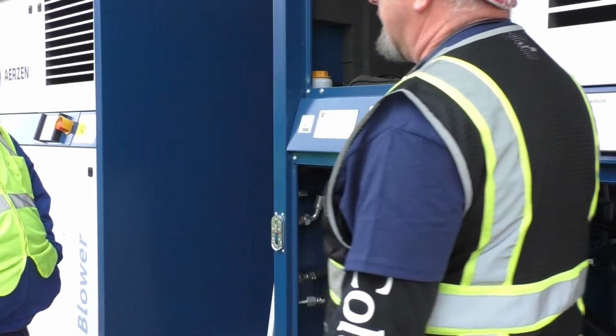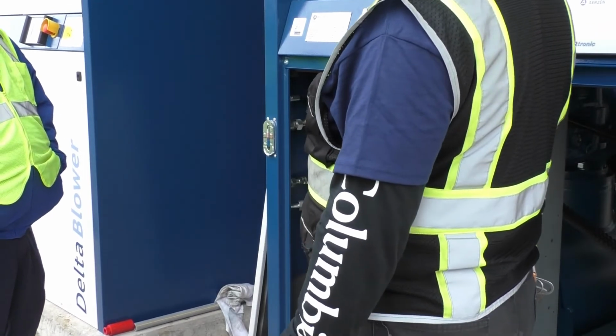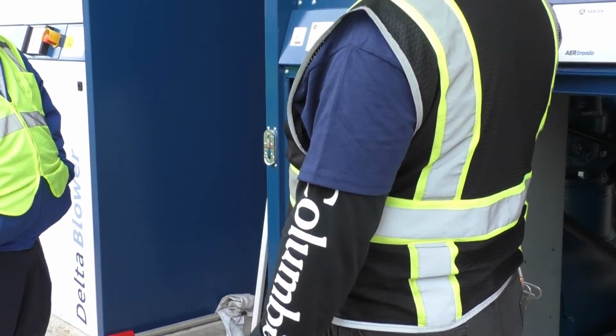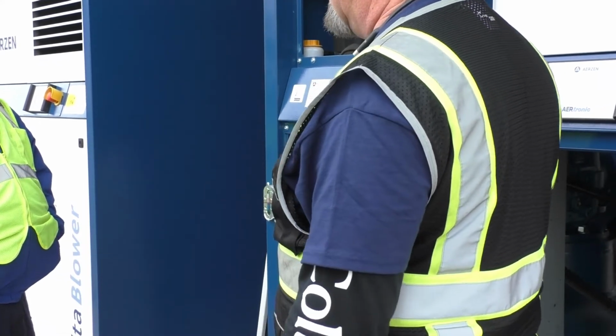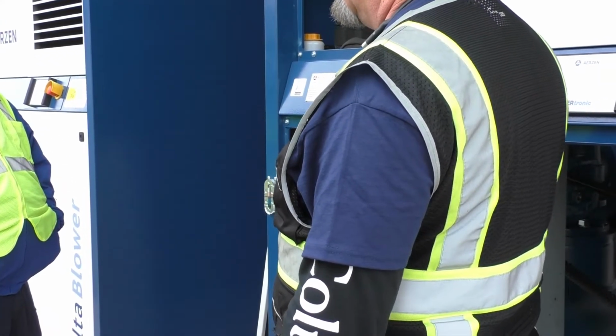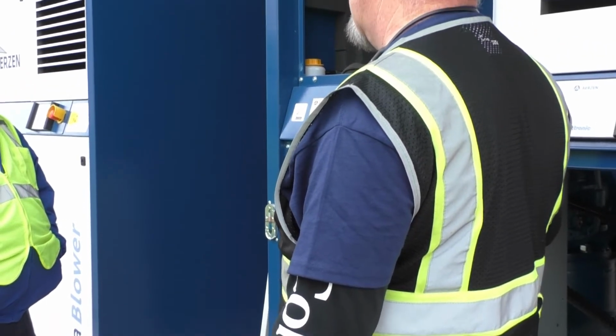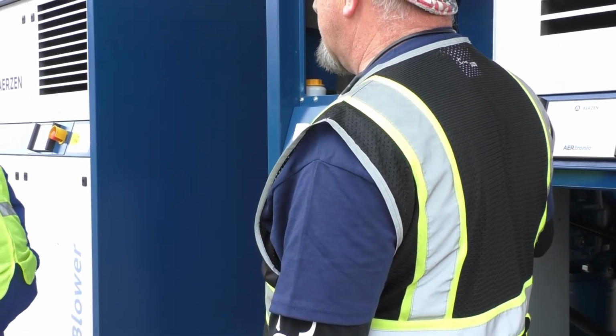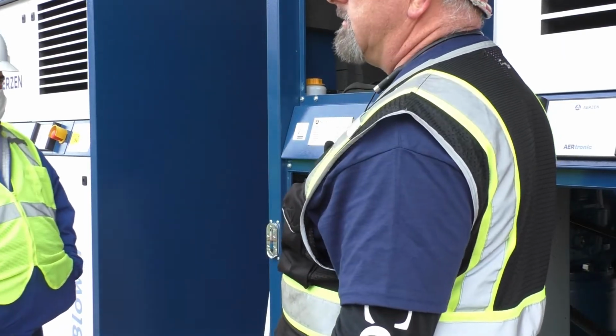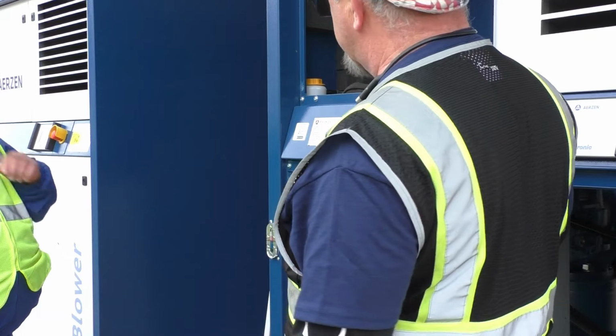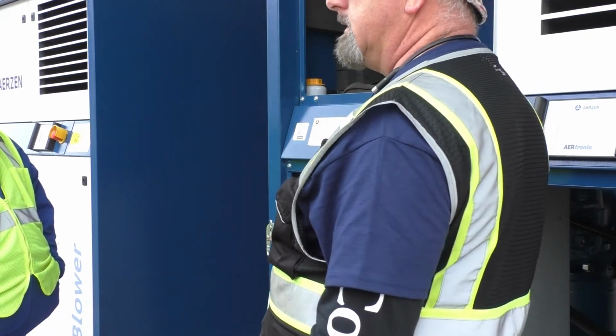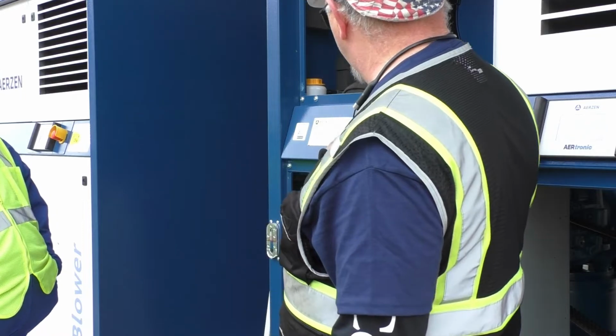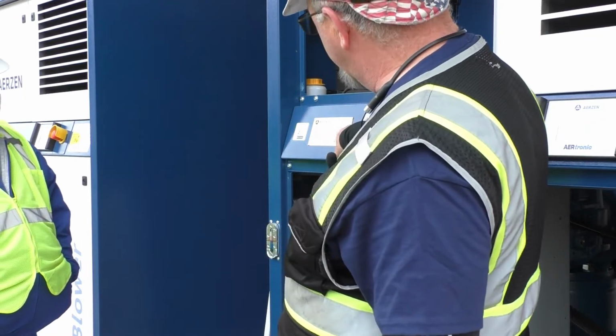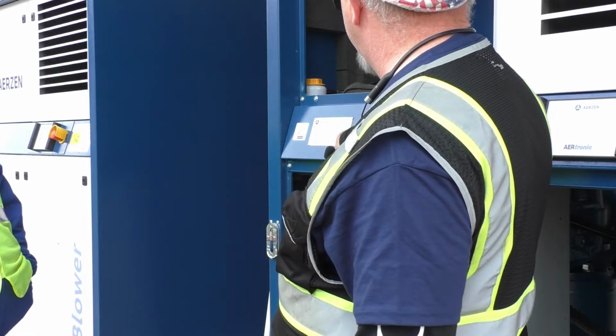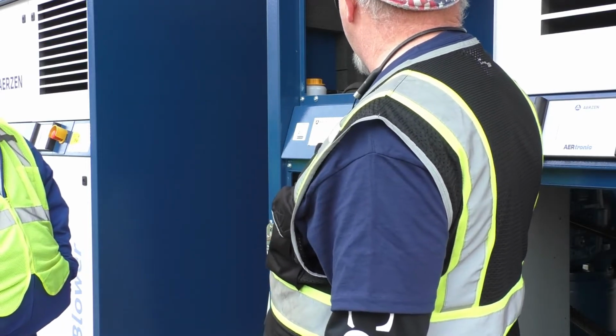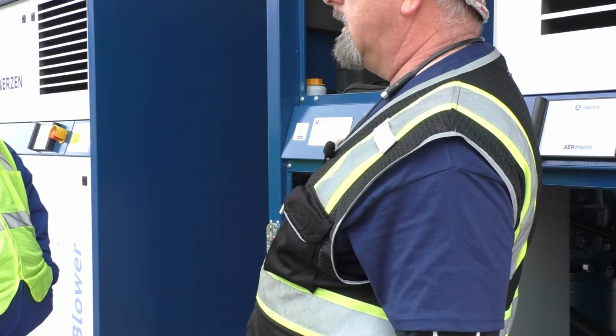I don't remember off the top of my head. I know a 5-gallon pail and 1-gallon jug is enough to do every blower. I believe these are approximately just under a gallon each, if I remember correctly. I have all of it saved on my laptop, and it is listed in the manual. They give you all the different blower sizes and the quantities of oil that they use. On the ID tag, it gives you your 800 number, your email address, what the air filter part number is, the quantity and part number of belt, and the oil type.